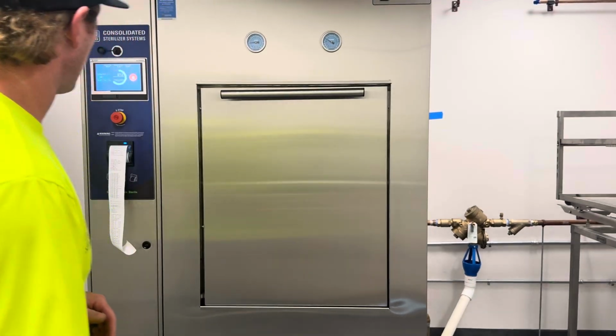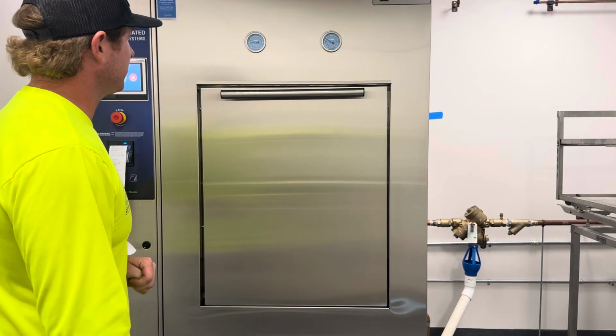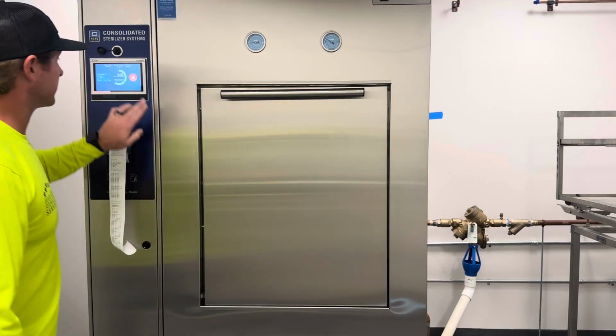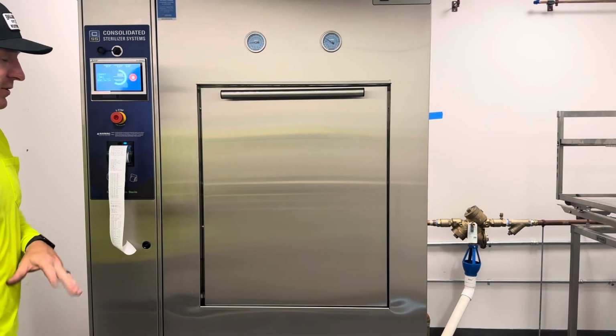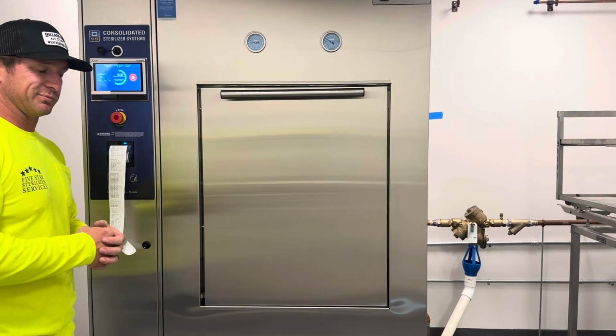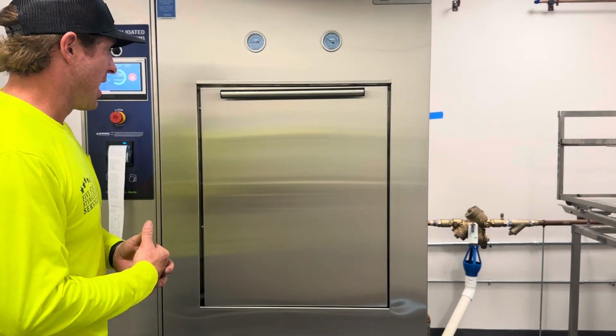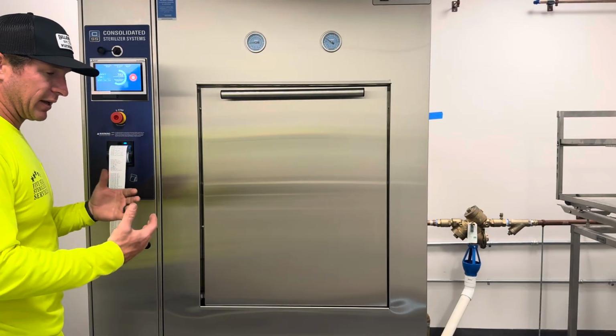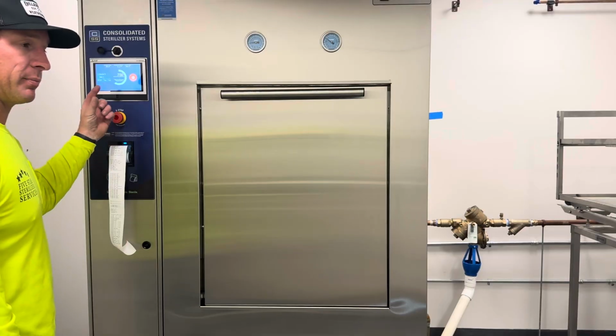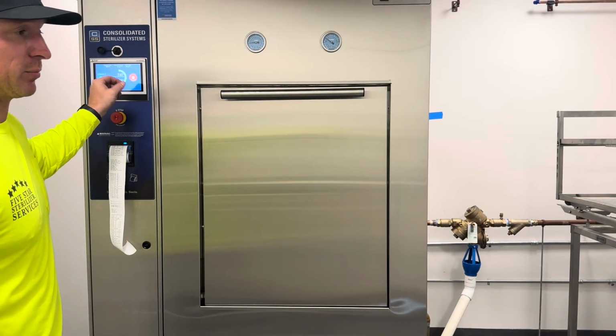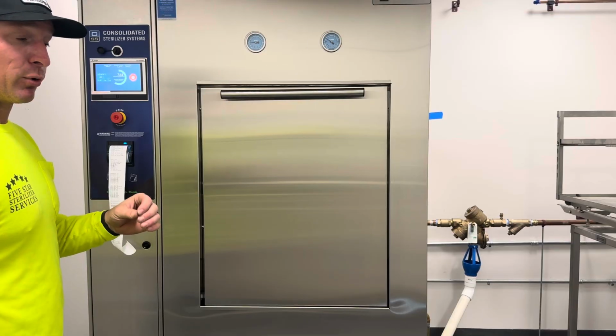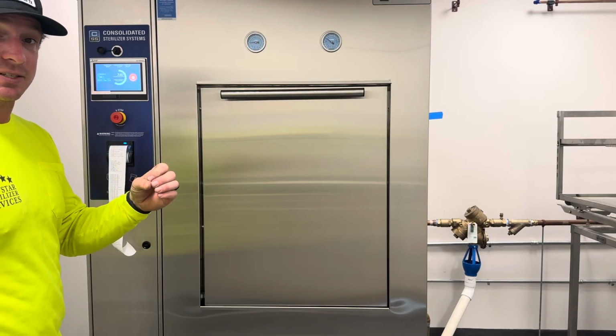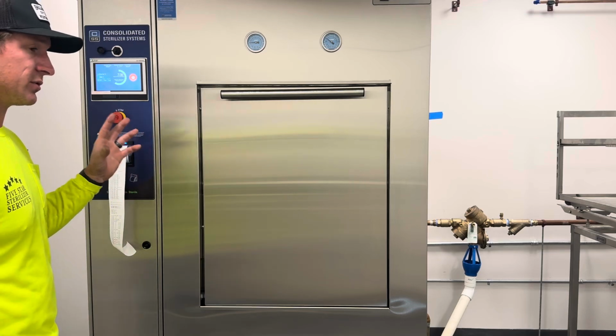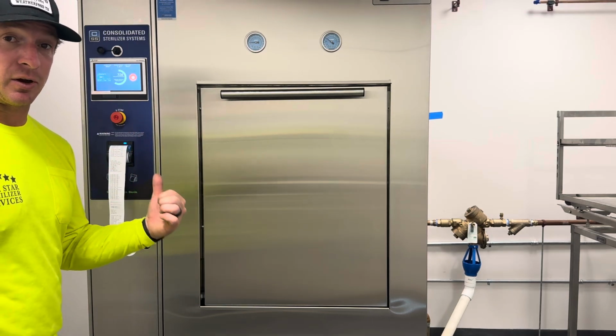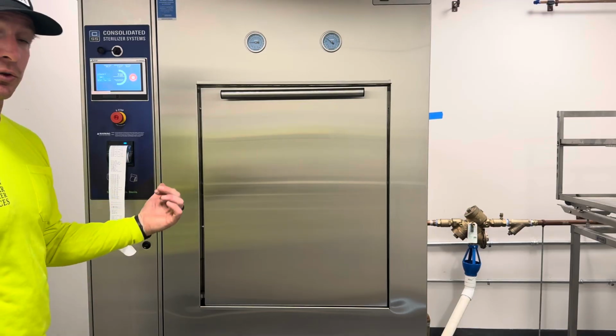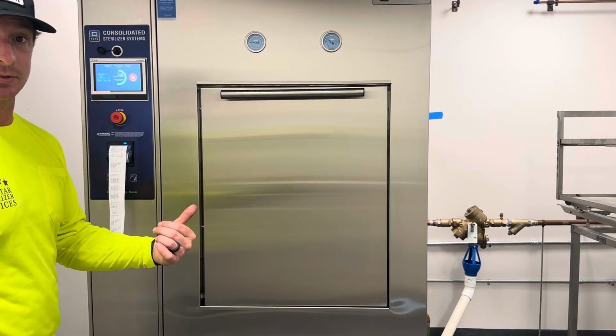If you ever need to abort a cycle, which I'm not going to do just yet, you can see on the screen this big red button on the side. So say you started a cycle, but you forgot some glass that you're trying to sterilize. You can press abort this cycle. It's going to prompt another window that says, are you sure you want to abort the cycle? You press yes. At that point, it will go through the exhaust phase of whichever cycle you have chosen. So if you have a 5-minute dry time on a gravity or vacuum cycle, it's going to go through that 5-minute dry time before it aborts the entire cycle.